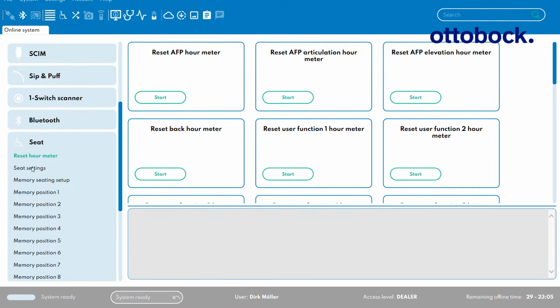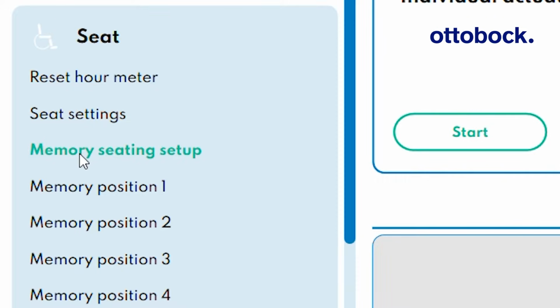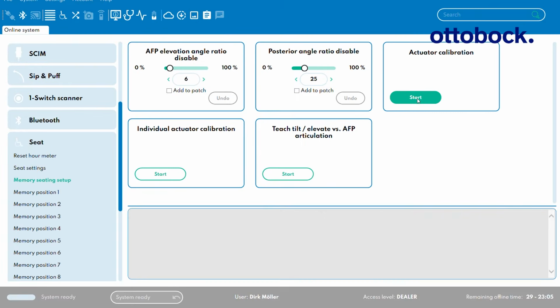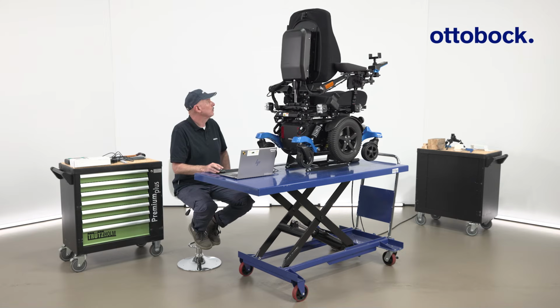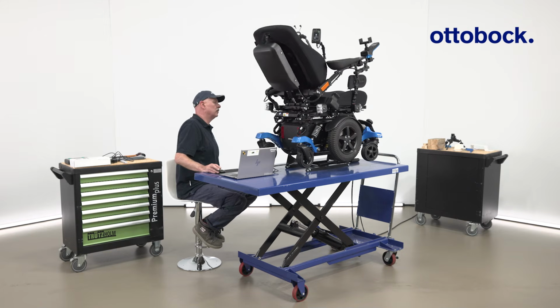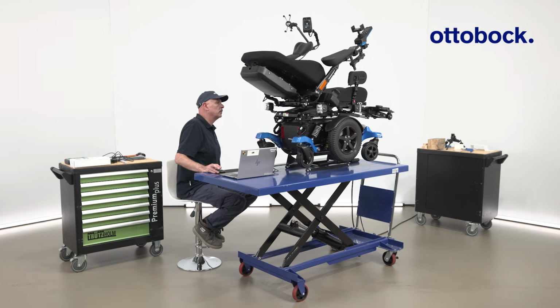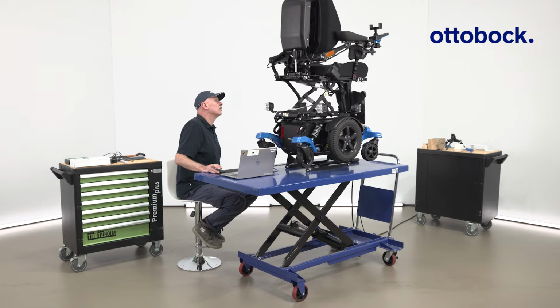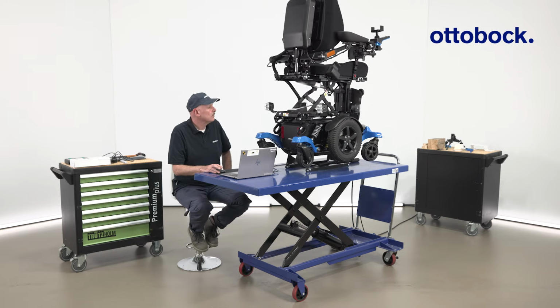To do this, open the Seat menu in the ECON-W Programming Station and select Memory Seating Setup. Then start Actuator Calibration. During the calibration process, no person may be seated in the wheelchair. The procedure must be monitored at all times.